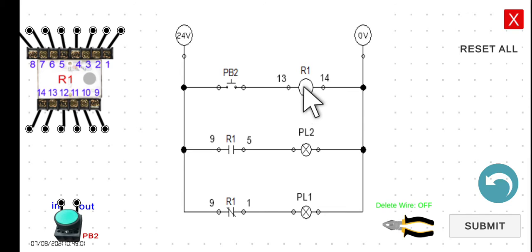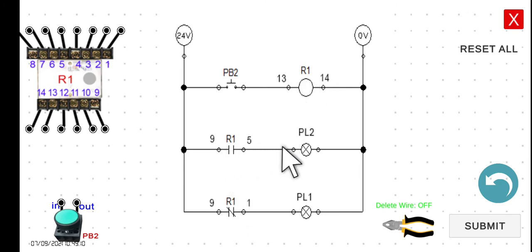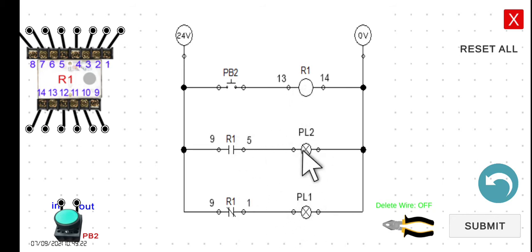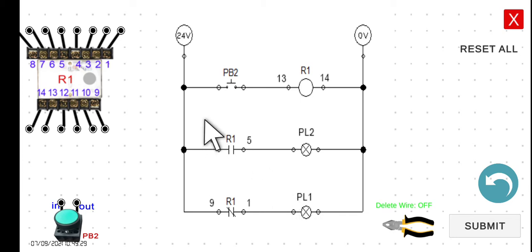However, if we press PB2, R1 will be in its energized form. The normally open contact will close and the normally closed contact will open. When the normally open closes, PL2 will turn on. When the normally closed opens, PL1 will turn off. If we release it again, it de-energizes: PL2 turns off and PL1 turns on — these are the alternating lamps.